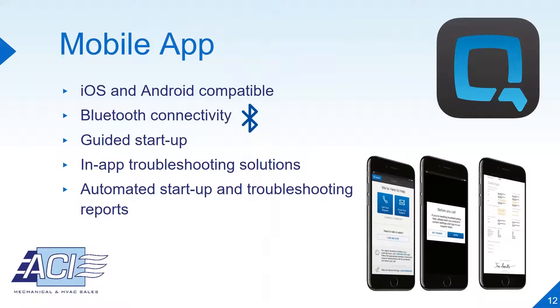Q-Link's mobile app is iOS and Android compatible with monitoring via Bluetooth connectivity. It offers a simple and intuitive user experience that expedites the setup and support process. It has the ability to save and store device settings along with creating configuration templates. The app has over-the-air firmware updates and a guided startup, which simplifies the difficult startup process of other VFDs. The troubleshooting solutions through the app are also fantastic, as there is sequential app support and live support if needed. By providing remote monitoring and control through the app, it enhances safety by minimizing the need to interact with the drive. Lastly, the app produces automated startup and troubleshooting VFD reports.